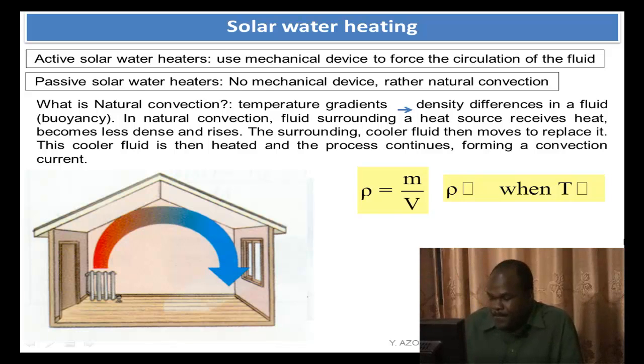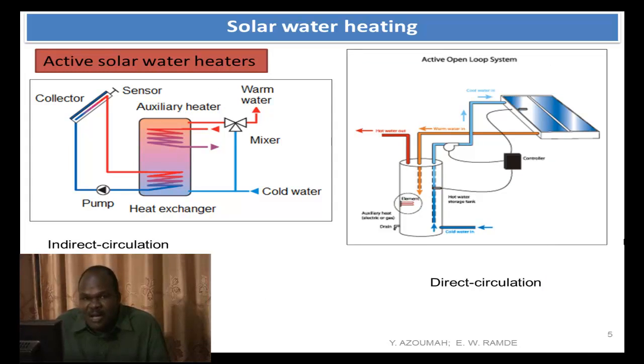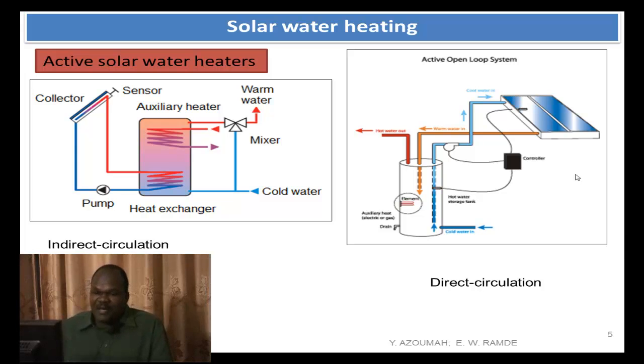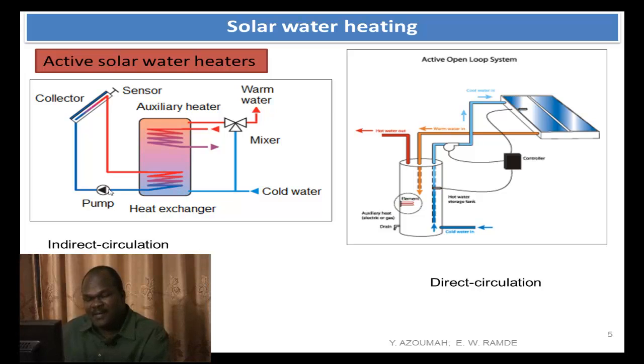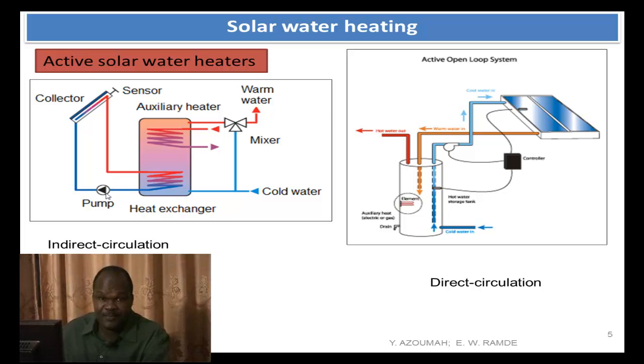These pictures are showing active solar water heaters. The left-hand side shows an indirect circulation, and the right-hand side shows a direct circulation. They are all active solar water heaters because they use pumps to circulate the water — you see the pump on the left-hand side and the pump on the right-hand side. Now, one is indirect and the other is direct. In the indirect solar water heaters, you have two loops, or let's say two fluids.